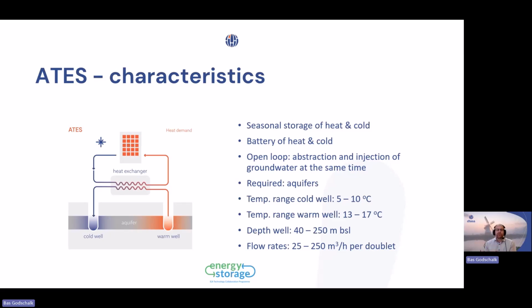Typical temperature range for cold is between 5 to 10 degrees, and typical abstraction temperatures from the warm well are between 13 to 17 degrees. In cooling mode, you can use the low temperatures for direct cooling of your building. In heating mode, you still need a heat pump to raise the temperature to 45-50 degrees to heat the building. Typical flow rates are between 25 to 250 cubic meters per hour, and wells are often installed at depths of 40 to 250 meters below surface, depending on where the best aquifer is located.